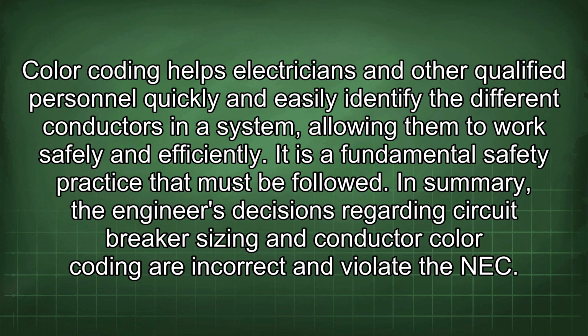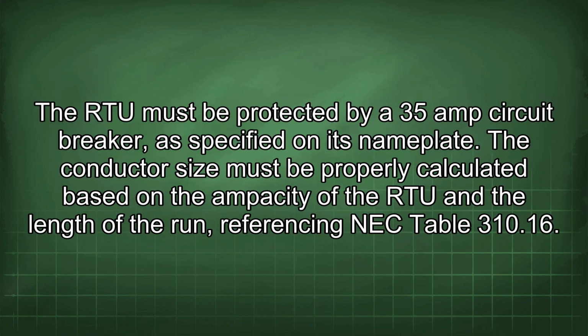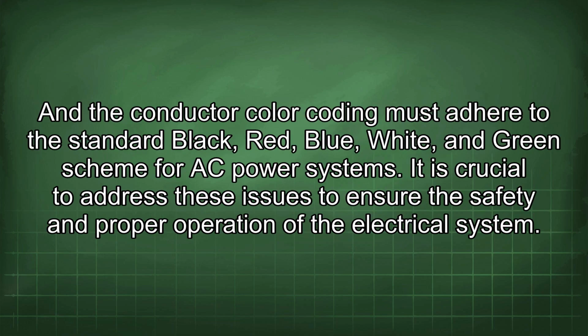In summary, the engineer's decisions regarding circuit breaker sizing and conductor color coding are incorrect and violate the NEC. The RTU must be protected by a 35 amp circuit breaker, as specified on its nameplate. The conductor size must be properly calculated based on the ampacity of the RTU and the length of the run, referencing NEC Table 310.16. And the conductor color coding must adhere to the standard black, red, blue, white, and green scheme for AC power systems.